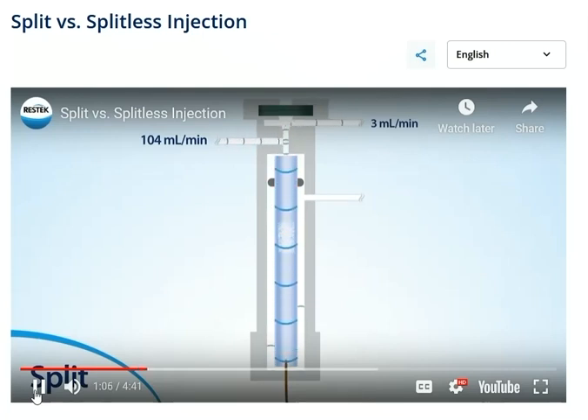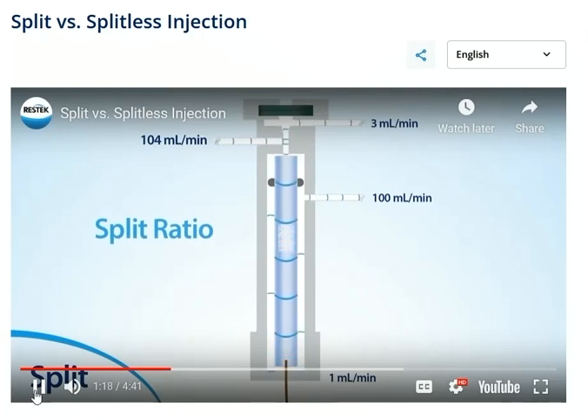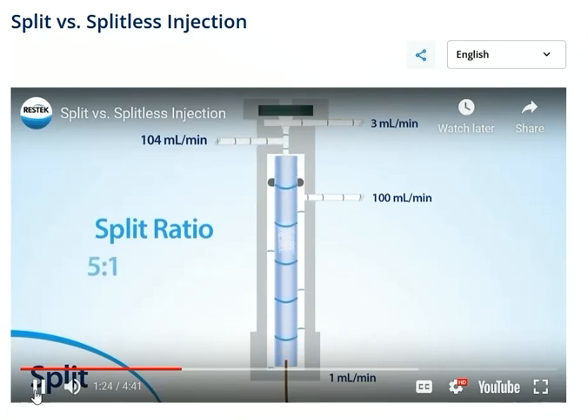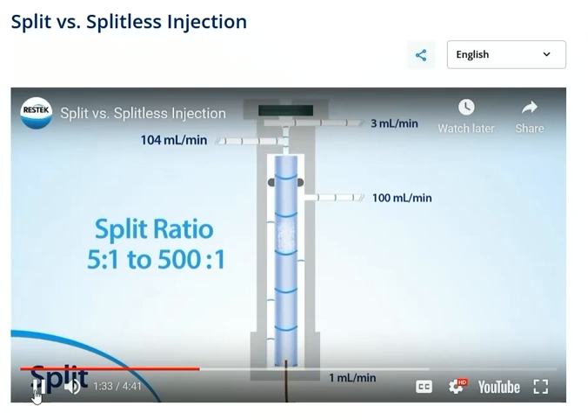A fraction of the gas — 1 mil per minute — flowed into the column, but most — 100 mils per minute — is swept away via the split vent. This ratio, the split ratio, is determined by the user before starting the analysis. Split ratios typically vary between 5 to 1 to 500 to 1. The higher the ratio, the lower the amount of sample that enters the column compared to what passes out the split vent.